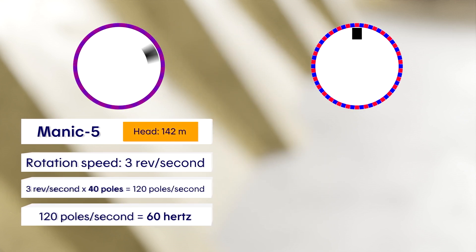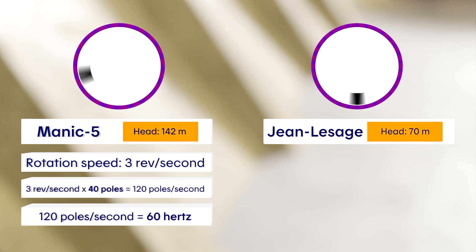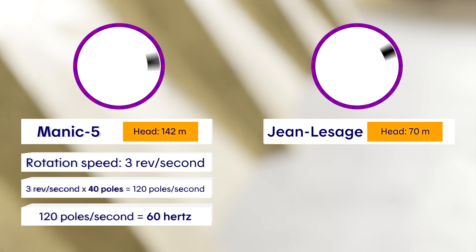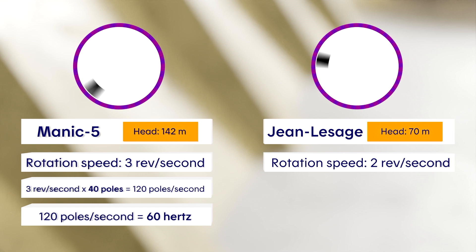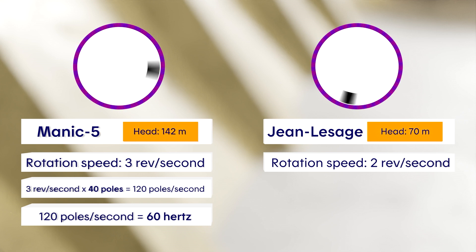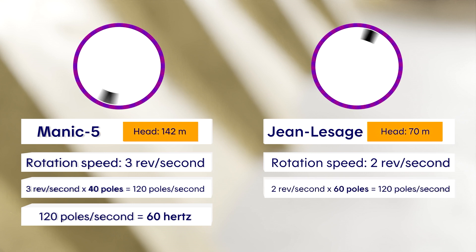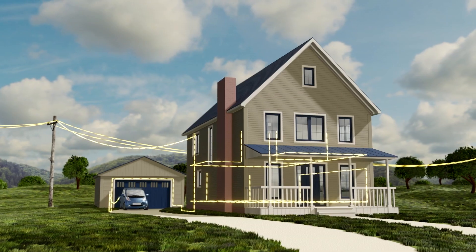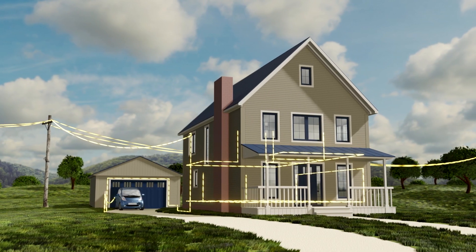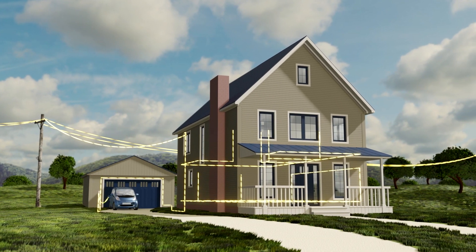Let's apply the same logic to Jean Lesage's generating station, where the hydraulic head is lower. There, the rotation speed of the rotor is lower, at 2 revolutions per second. At 2 revolutions per second, how many poles does the rotor need to reach a frequency of 60 hertz? The rotor makes 2 revolutions per second, so it takes 60 poles to reach 120 poles per second. Remember that 120 poles per second is equivalent to 60 hertz. So the frequency is the same across Quebec's power grid: 60 hertz.